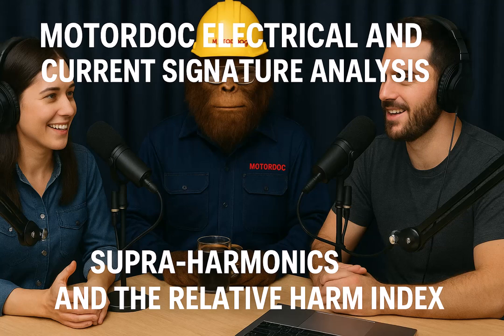It sounds like getting good data is important here, requires some care. Absolutely. You need enough data collection time and the right sample rate to get good frequency resolution. Resolution meaning? Meaning you can clearly distinguish between frequencies that are very close together. The research mentioned, for instance, collecting ESA data for about 48 seconds gives you a resolution of 0.02 hertz. Wow, very fine. Yeah, and that can be crucial to tell different potential problems apart.